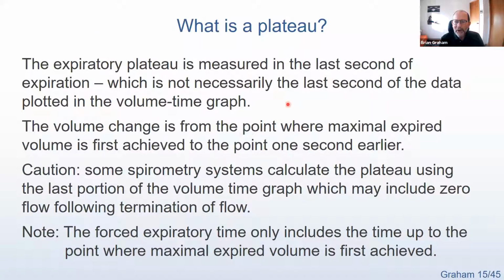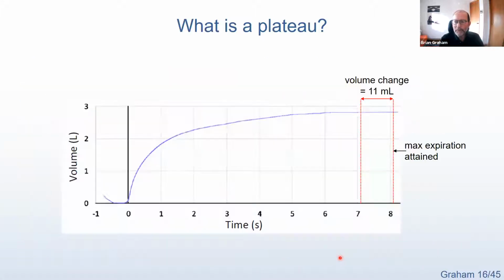So the question is, what is a plateau? Well, the plateau should be measured in the last second of expiration. And too often I've seen it measured in the last second of the volume time graph, which is not necessarily the same thing. So the volume change that we measure for the plateau is from the point where maximal expired volume is first achieved to the point 1 second earlier. That's where you measure the plateau. And so in systems which just measure the end of whatever's been graphed, there could be some zero flow time in there, which is not part of a plateau. And similarly, the forced expiratory time only includes the time from the start of expiration to the point where maximal volume is first achieved. So let's look at some examples. So here's an example of a good blow.